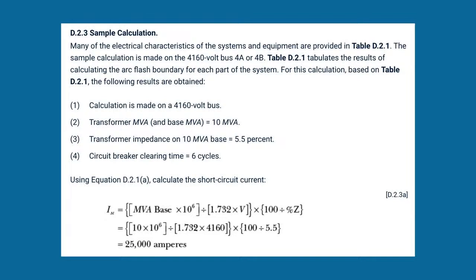Now, to get the short circuit current, you need the MVA base, which is 10, multiplied by 10 to the 6th power, divided by your voltage times 1.732 for three-phase. Then you use a common denominator of 100, divided by the impedance. You take that impedance and that voltage, multiply them, and divide into that base. When you perform this calculation, it gives you 25,000 amperes. That's my short circuit current.